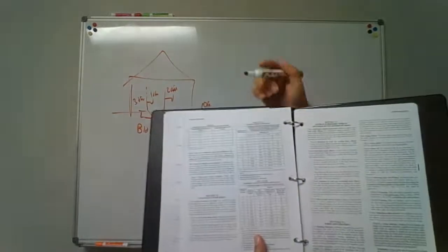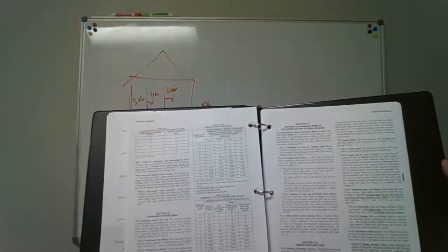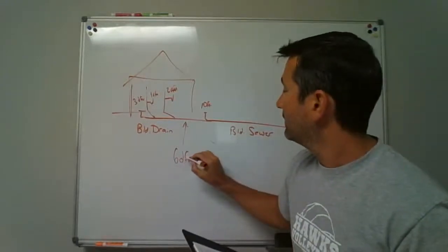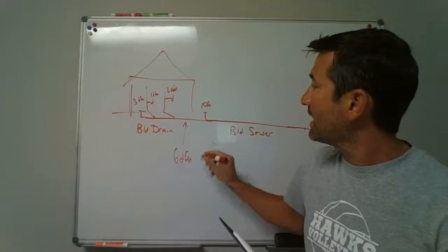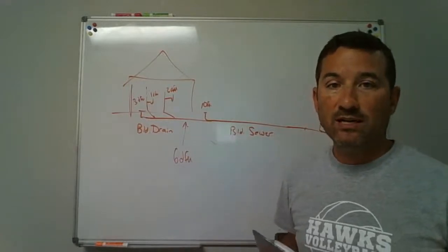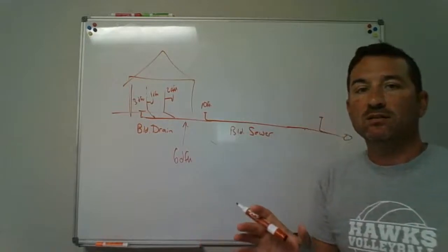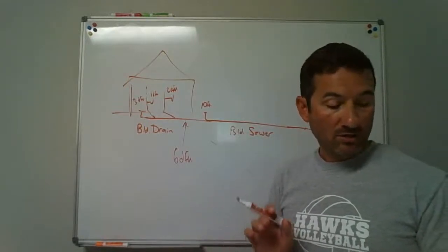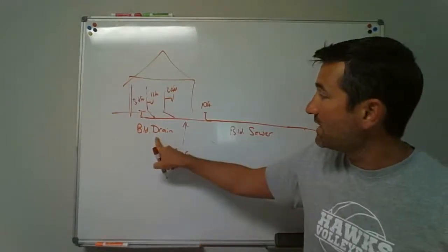And you say, okay, 6 DFUs. Oh, yeah, a 2-inch pipe can handle it. A 2-inch can handle up to 21 DFUs, even run at its minimum slope. But it says, no, we got a water closet, so the main drain has to at least be 3 inches. So even though if you look at it strictly by the numbers, you can say, oh, we can do it strictly by the numbers, but it's got a note on there that says no less than 3 inch. It's the minimum size building drain.